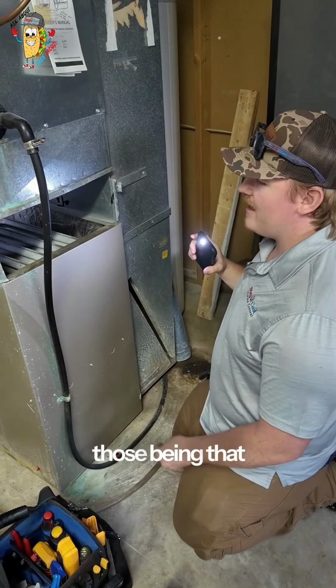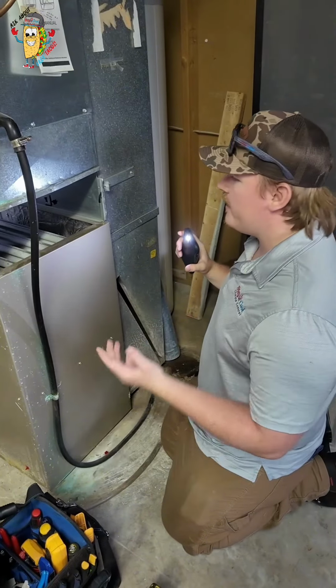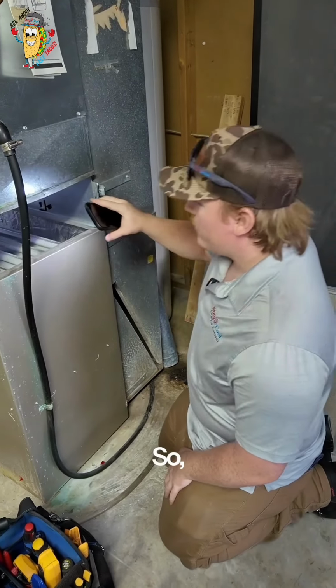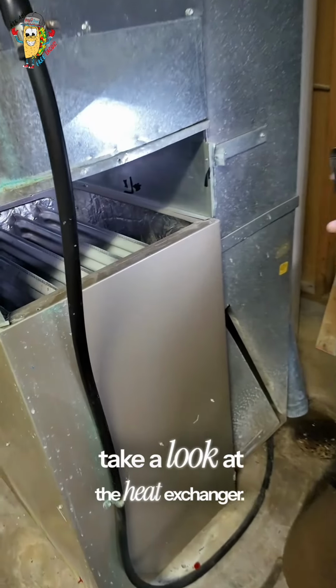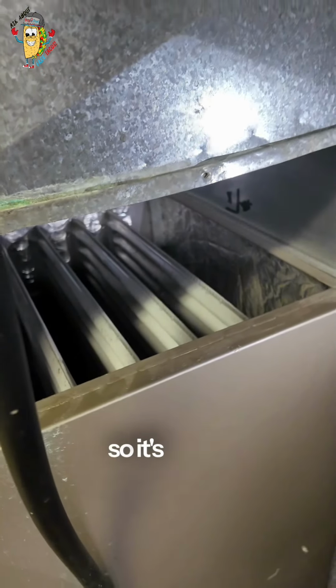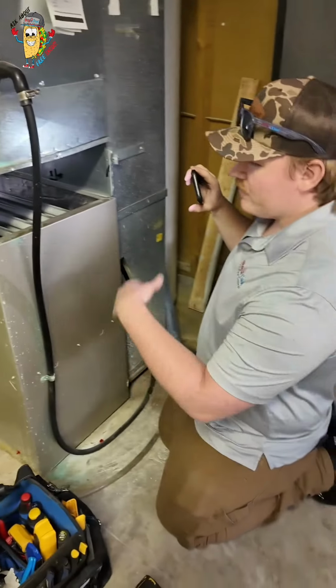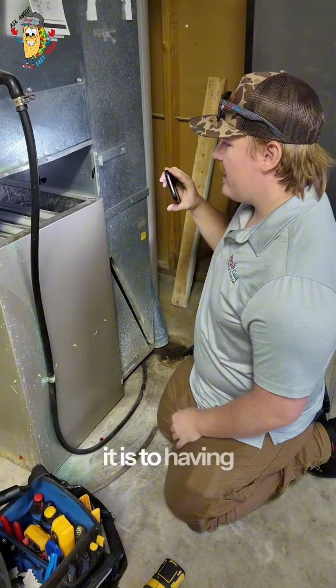So while doing our furnace inspection, we noticed a few different symptoms of issues with the heat exchanger. Those being that the temperature rise was very high, and the flames were flickering orange. So we decided to get in here and take a look at the heat exchanger. This furnace is from 2011, so it's about 14 years old as well. The longer a furnace has been around, the more prone it is to having these issues.